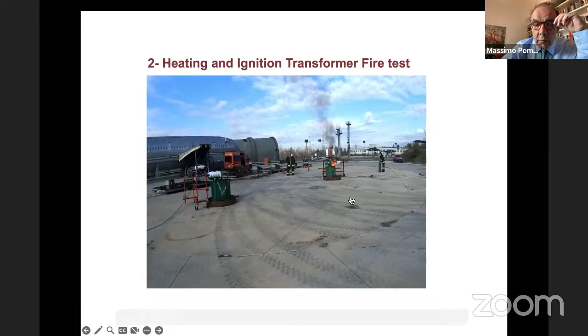So we started heating the transformer. We put two probes, one in the upper part of the transformer, and the probe called B in the lower part. Looking at the upper part, we can compare the orange line with the green line. In the case of the green line, we started heating the oil. Temperature is slowly increasing, and heating goes on. After 1 hour, nothing happened. Maximum temperature was something like 80 degrees, but no fire, nothing happened.